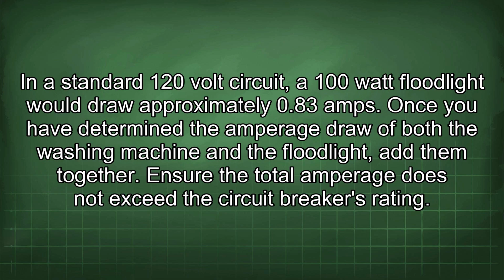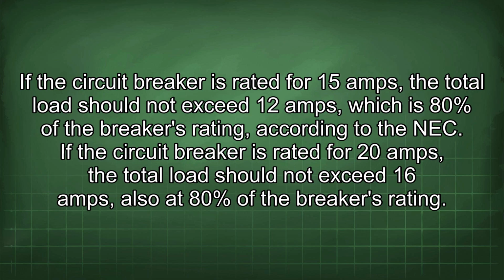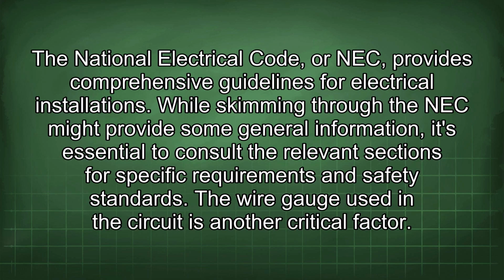Once you have determined the amperage draw of both the washing machine and the floodlight, add them together. Ensure the total amperage does not exceed the circuit breaker's rating. If the circuit breaker is rated for 15 amps, the total load should not exceed 12 amps, which is 80% of the breaker's rating, according to the NEC. If the circuit breaker is rated for 20 amps, the total load should not exceed 16 amps, also at 80% of the breaker's rating. The National Electrical Code, or NEC, provides comprehensive guidelines for electrical installations.